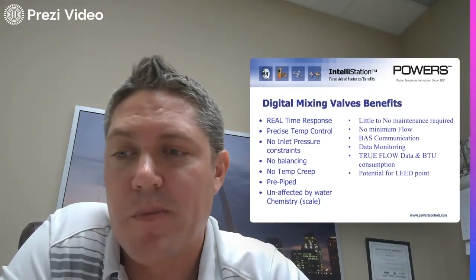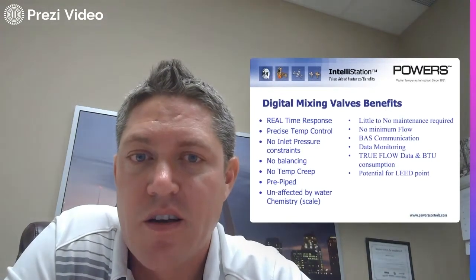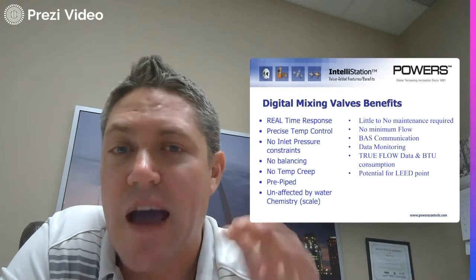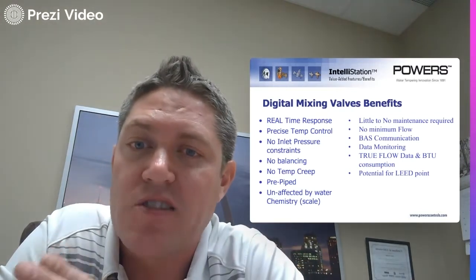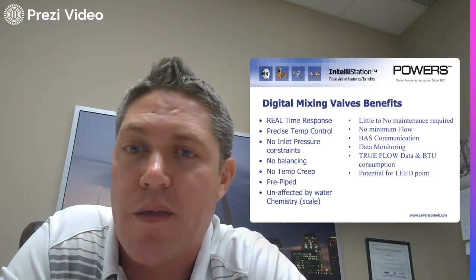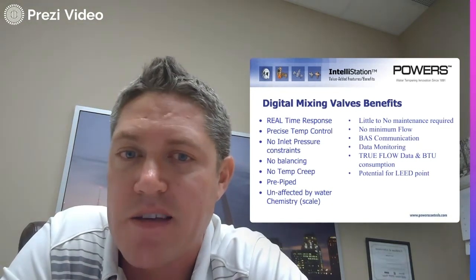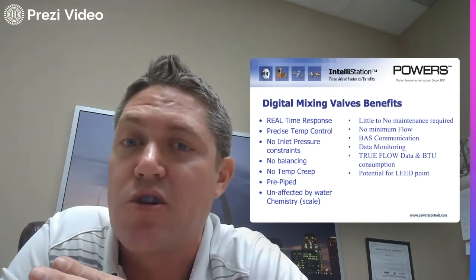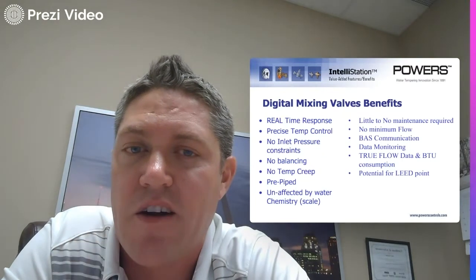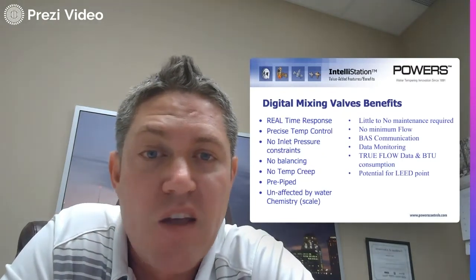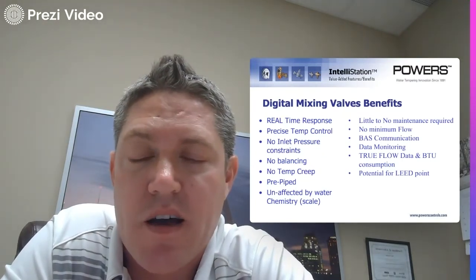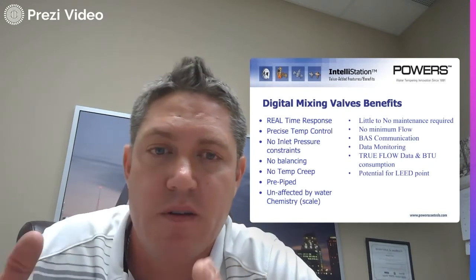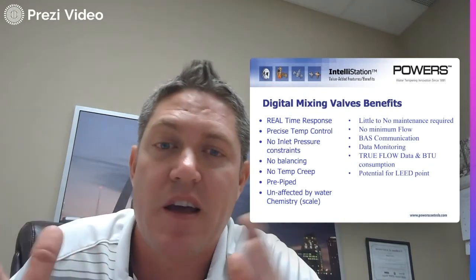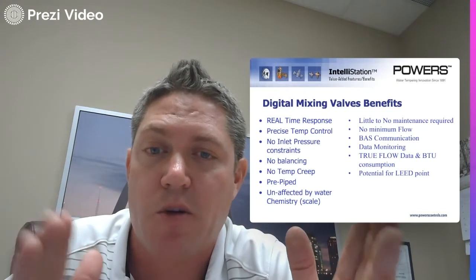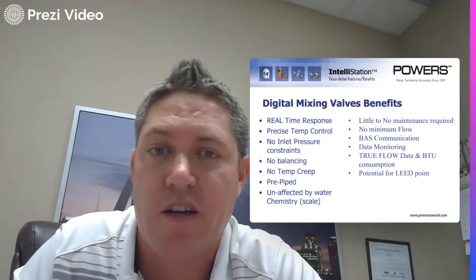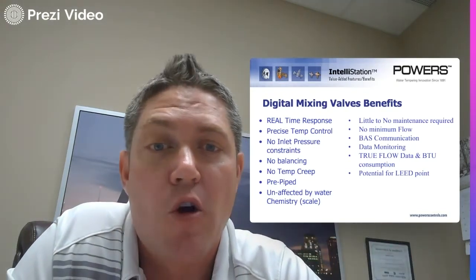Okay, so now let's talk a little bit about digital mixing valves. So, tighter temperature control. Where we were plus or minus 7 degrees from set point with the current technology for thermostatic master mixing valves, it's plus or minus 2 degrees from set point with digital. So tighter temperature control. No inlet pressure constraints. There can be a much larger differential between hot and cold pressure, and it'll still work on a digital. No balancing required.